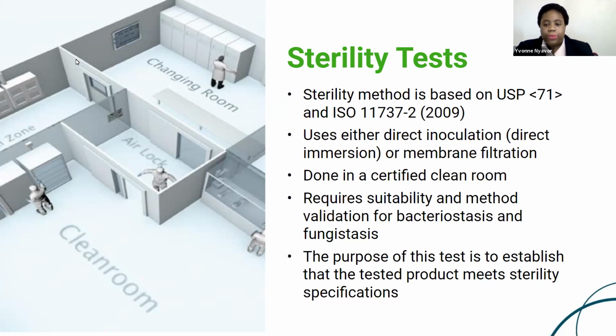And typically, we will use direct immersion with medical devices. However, in some cases, we'll use membrane filtration, especially if either bacteriostasis or fungistasis is detected, which basically means that after we immerse the device, or during suitability and validation, we notice that there is a component of that device that is impairing the growth of the microbes. And so to prevent that, we would then do a membrane filtration and wash, which will typically get rid of that inhibitory factor. So that's it for sterility testing.